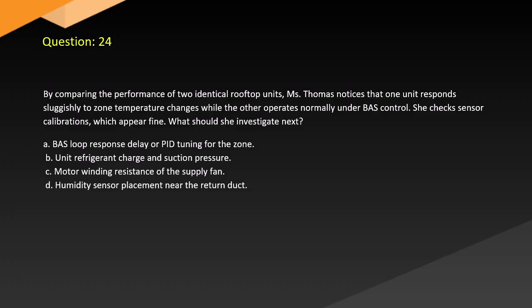Question 24. By comparing the performance of two identical rooftop units, Thomas notices that one unit responds sluggishly to zone temperature changes while the other operates normally under BAS control. She checks sensor calibrations, which appear fine. What should she investigate next? A. BAS loop response delay or PID tuning for the zone. B. Unit refrigerant charge and suction pressure. C. Motor winding resistance of the supply fan. D. Humidity sensor placement near the return duct.